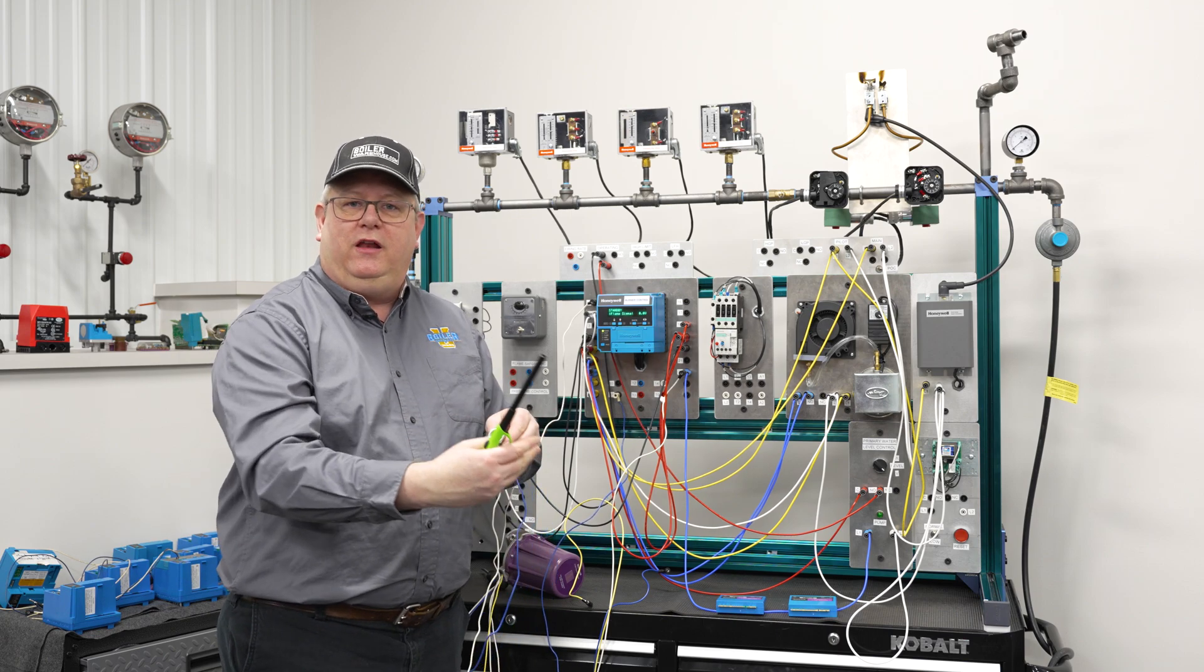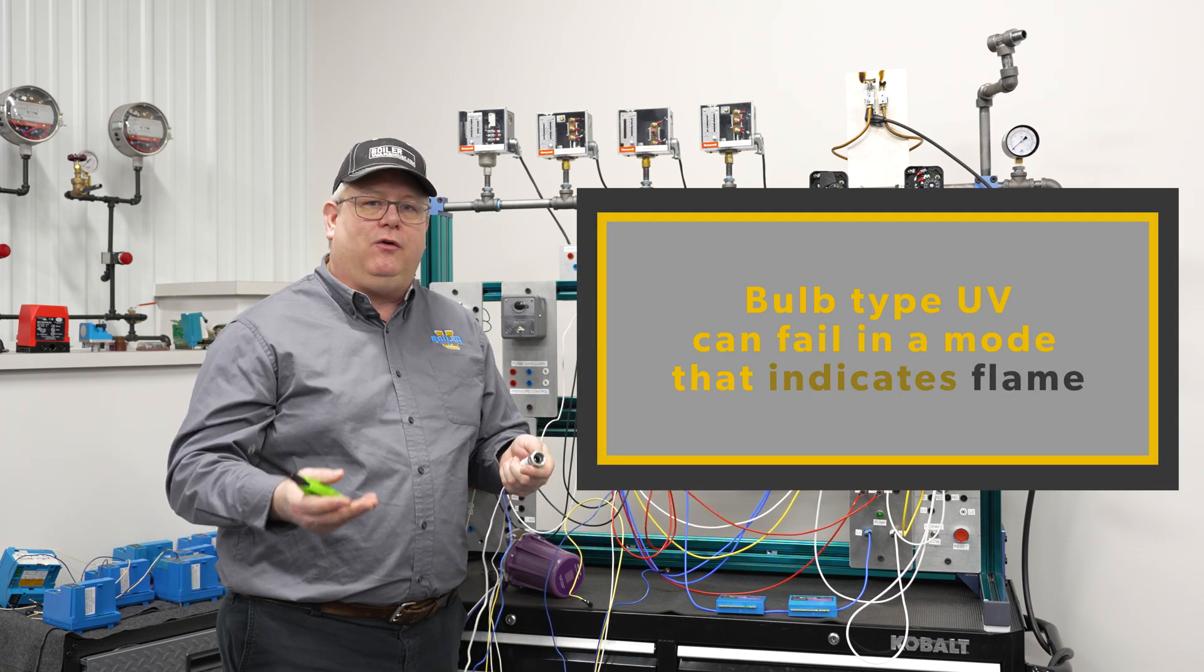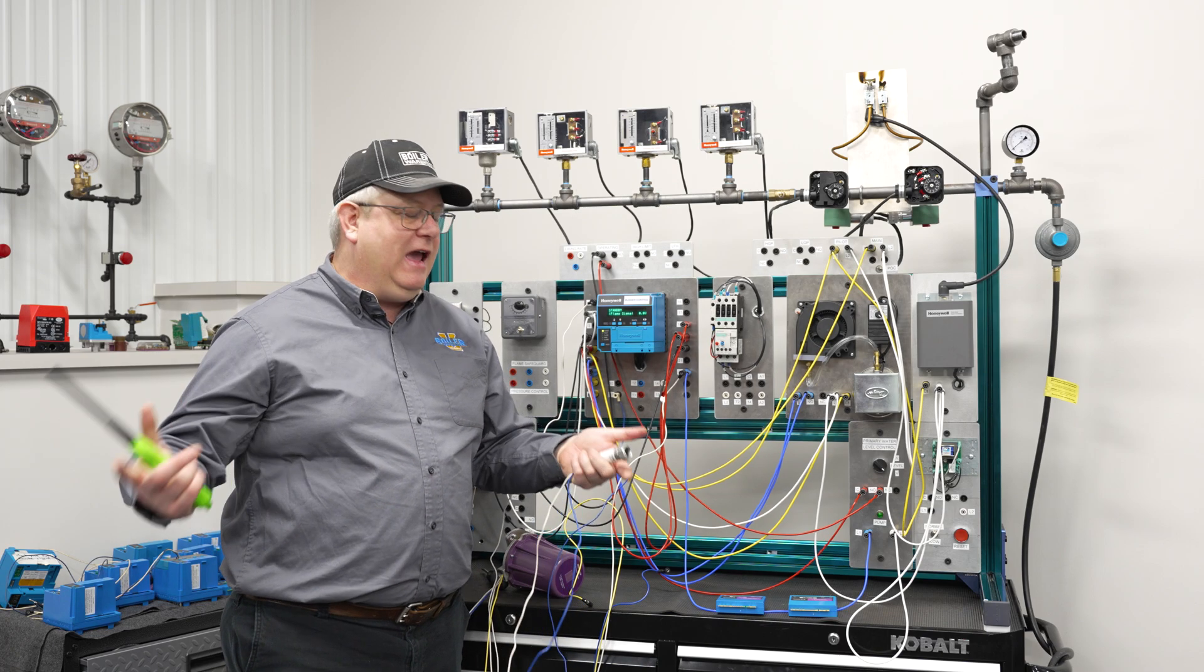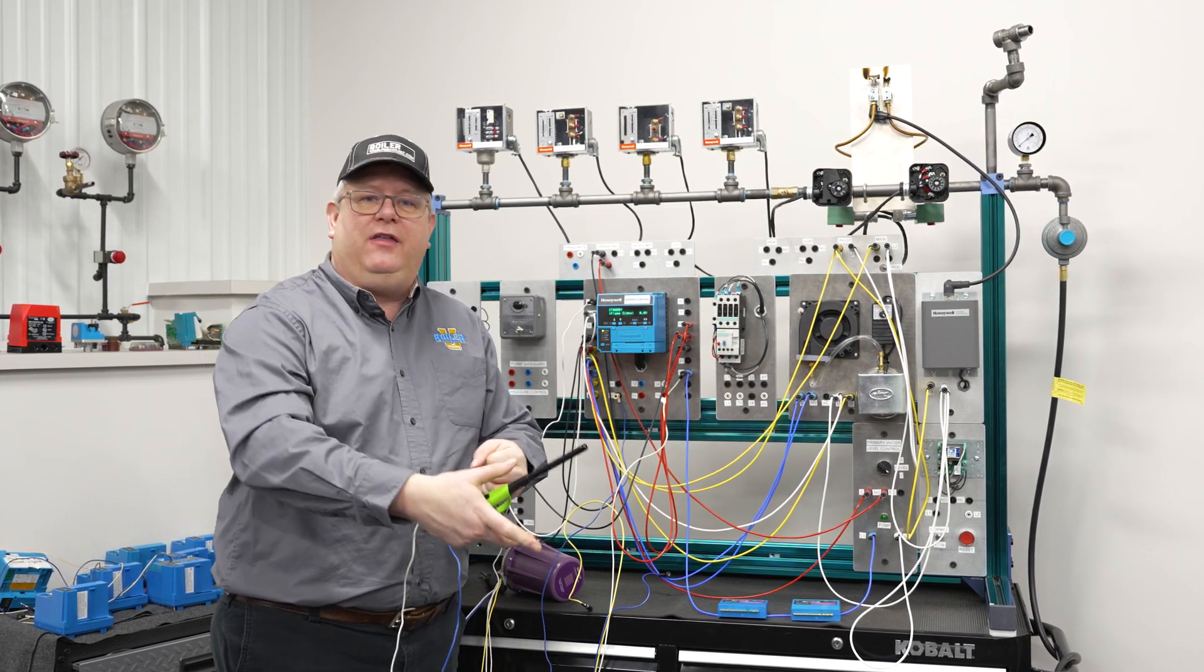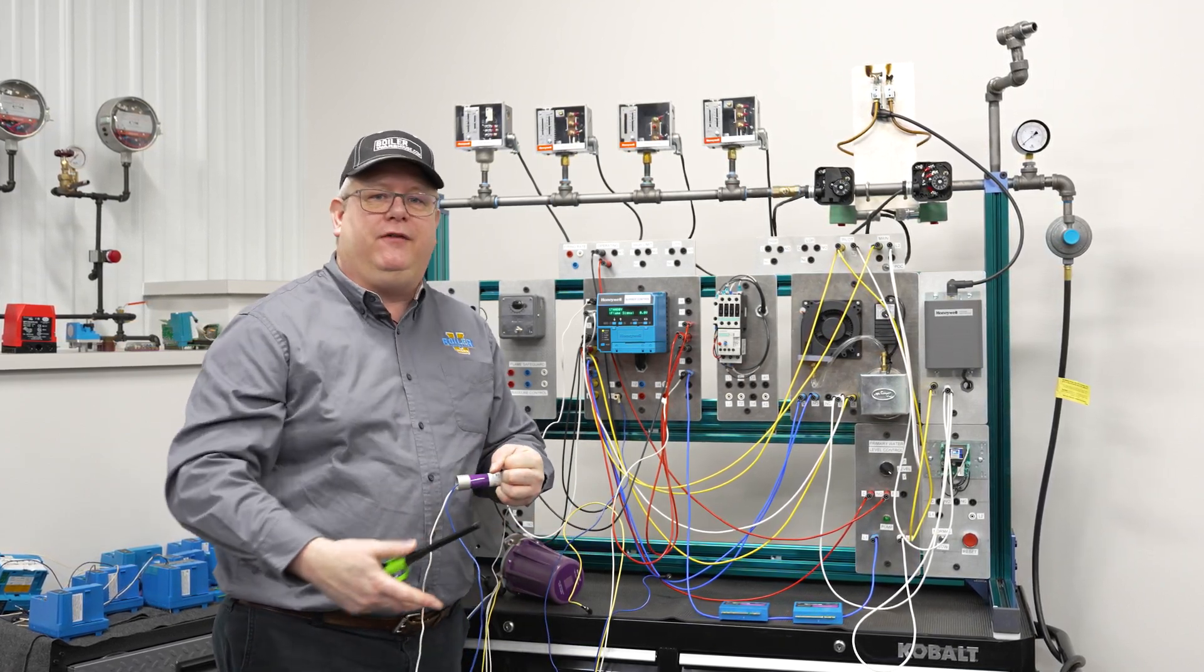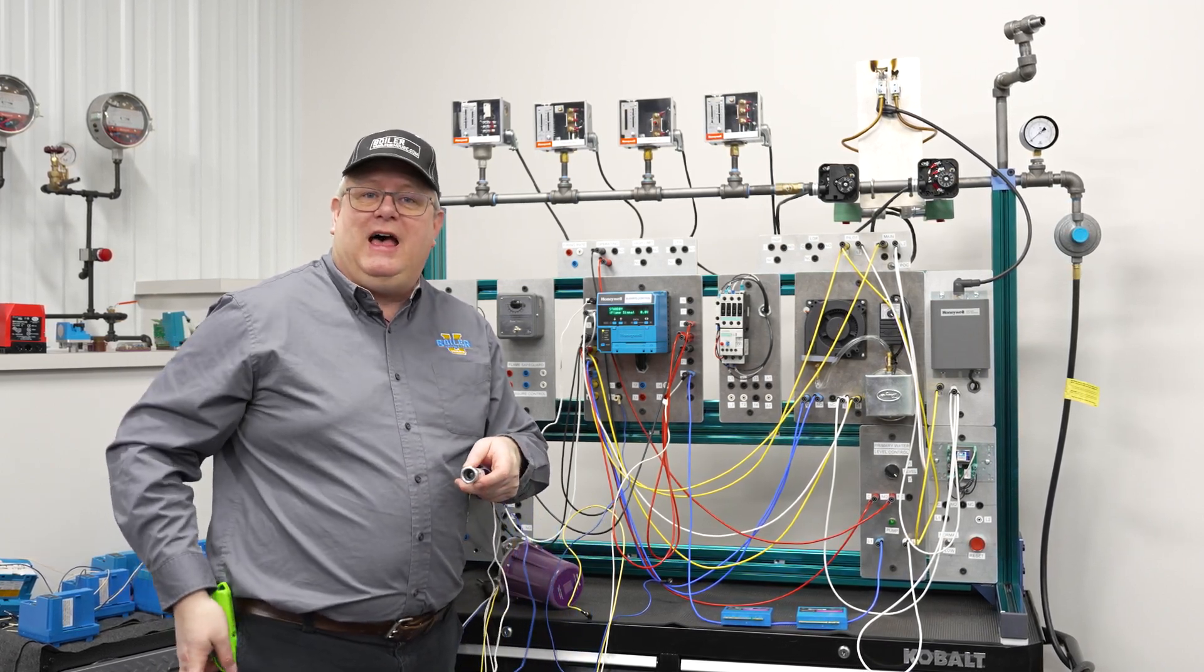The issue with a bulb-type UV is that it can fail in a mode that indicates flame. So while occasionally I may pull a scanner off, cover the top, and verify that it fails on flame failure, if we're not doing that test and we lose flame...